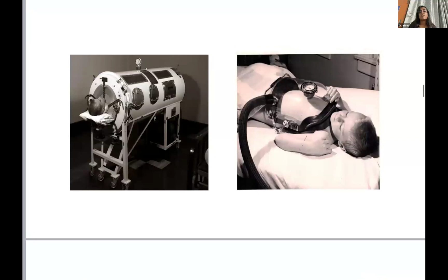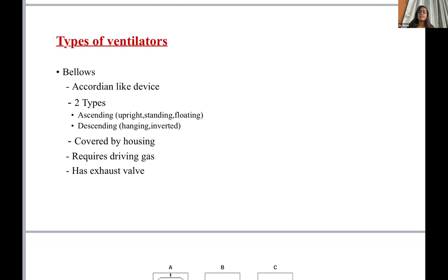Next, depending on the driving mechanism for inspiration and expiration, there are two devices which can be used, that is the bellows and the piston mechanism. So bellows is an accordion-like device which is actually of two types, that is ascending and descending type, based on its attachment to the bellows assembly circuit. Ascending type is also called the upright, standing or floating type. Descending type is also called the hanging or inverted type. The bellows circuit is covered by a housing unit, which is made up of a transparent plastic cylinder, which helps in visualization of the bellows during its movement during inspiration and expiration. The mechanism on which it works is given in this diagram.